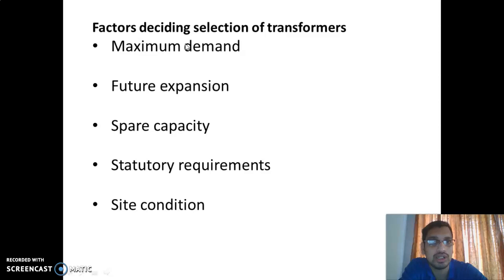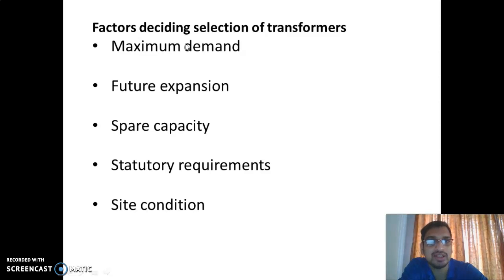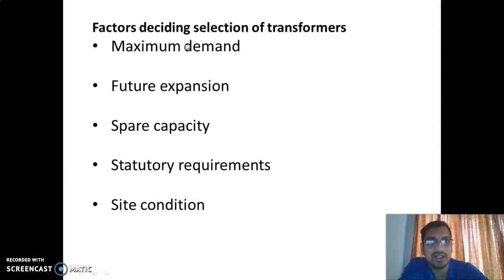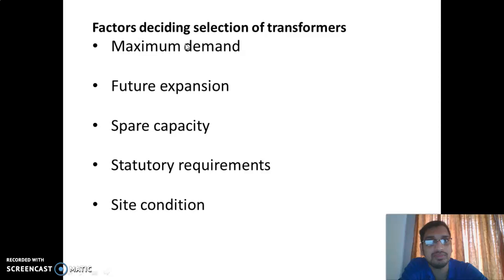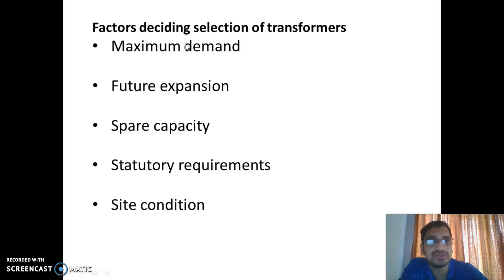Maximum demand equals connected load divided by diversity factor. Normally in industries, we assume the diversity factor is from 1.2 to 1.5. The maximum demand is less than the connected load. If the diversity factor is 1, both maximum demand and connected load are equal. In practical industrial cases, the diversity factor ranges from 1.2 to 1.5, though some factories consider a diversity factor of 1. Based on the maximum demand, we select the proper sizing of transformer.